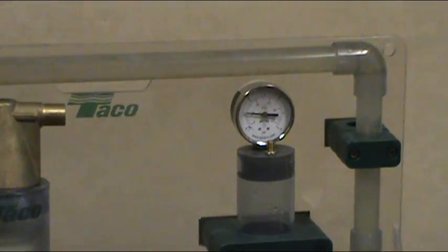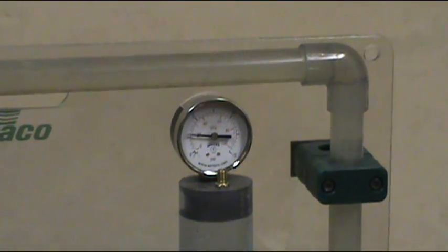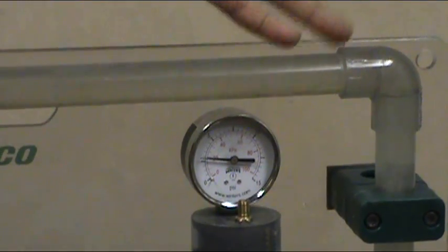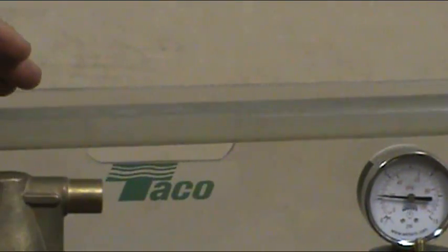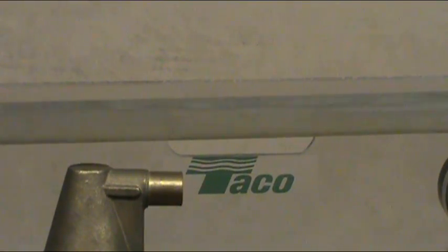One of the rules of thumb with a traditional air scoop is that you put it 18 inches from the elbow. The reason is that these bubbles have to rise to the top of the pipes, and it takes distance. In a typical heating system, it's around 18 inches.